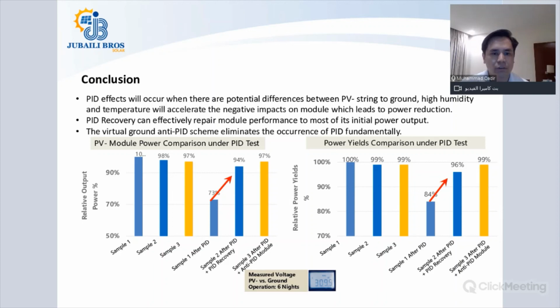So, the conclusion of the presentation: PID effects will occur when there is a potential difference between the PV negative string to ground in high humidity areas and high temperature areas. These will be accelerated, and it will have negative impacts on PV modules, which leads to power reduction. And PID recovery can effectively repair module performance to most of its initial power output. It cannot make it maybe 100% as it is on the PV module on the first day of its use, but it will definitely repair it to almost as it was on the first day of its usage.